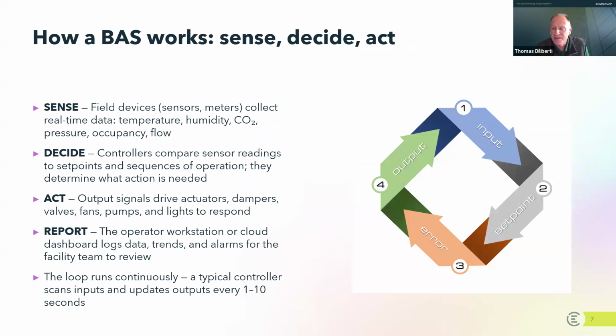And this is, again, a simplified version of what's happening, just a high-level understanding. But using the graphic here to teach this idea, first of all, the building automation system has to take inputs. So it's sensing something out in the field. It might be sensing temperature or humidity or carbon dioxide. It's taking some type of input. And the second thing it does is compare that input to a set point. So there's a set point that's identified by the user, and it's making the decision that it's either meeting that set point or it's not.